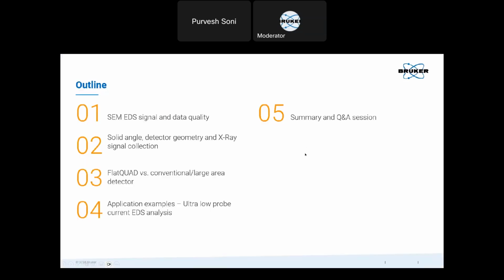And this is the outline of the talk. I'll start with the basics of the SEM EDS signal, how it is generated, and what affects the data quality during imaging and also during EDS mapping. We'll discuss shortly how solid angle and detector geometry also affect the signal collection. Then I'll present how FlatQUAD compares to conventional inclined or large area detectors. And that will be followed by application examples where I will show how FlatQUAD can be used at very low probe currents for EDS analysis. And then we'll end the session and the webinar with a summary and Q&A session.